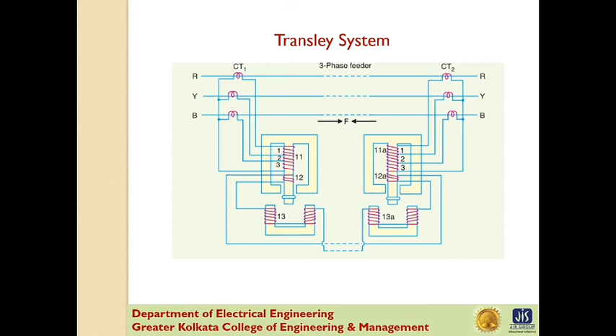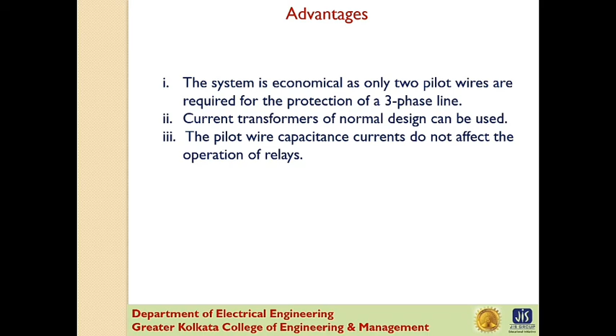Now, what are the advantages of this system? The system is economical as only 2 pilot wires are required for the protection of a 3-phase line. Current transformers of normal design can be used. The pilot wire capacitance current does not affect the operation of the relay.